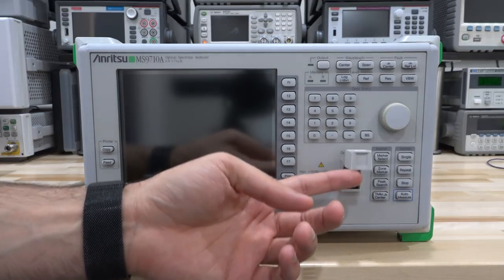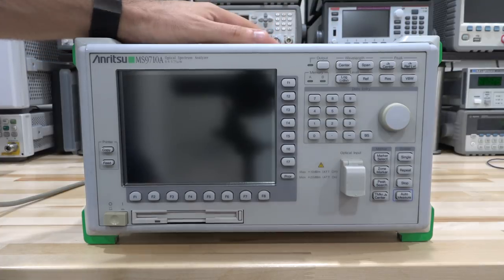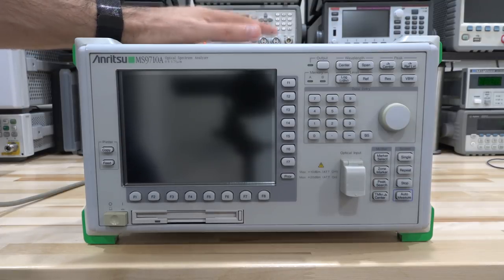And as you can see, there's an optical input in the front, and it looks like it's in good shape otherwise, but it doesn't work. We want to find out what's going on with it, and if we can fix it, it'll be great. The nice thing about this unit is that it's very small. Normally, optical spectrum analyzers are huge, primarily because a lot of them are based on free space optics, and that requires basically an optical table to be built into the unit, and it has a lot of moving parts, and therefore it's extremely heavy. This one is also very heavy, but it's not very large. So we're going to try it out.